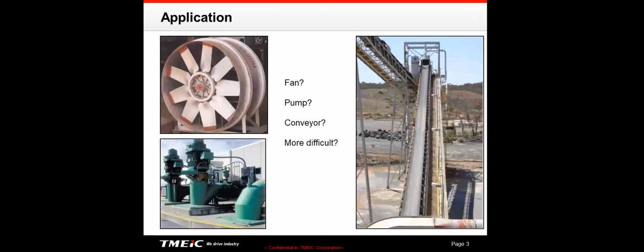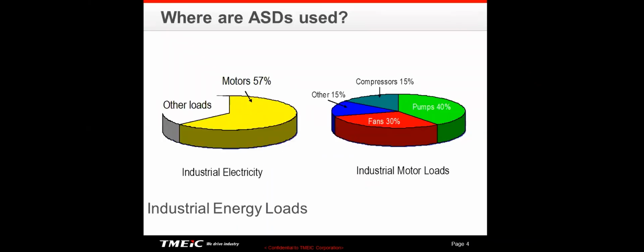The first thing is the application. Now, most medium voltage drives are put on fans, pumps, or conveyors, but there are a lot of more difficult applications. The biggest reason why variable frequency drives or adjustable speed drives are used, regardless whether it's low voltage or medium voltage, is for energy savings. Now, these are the market share in these various applications.